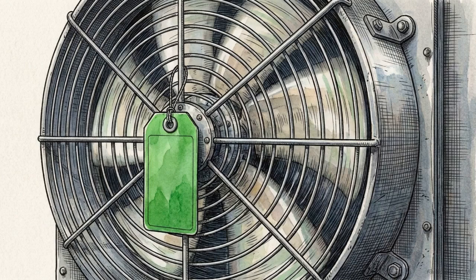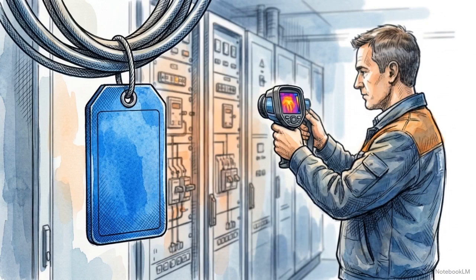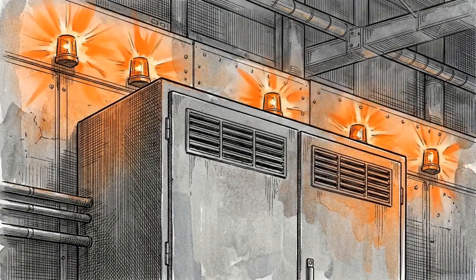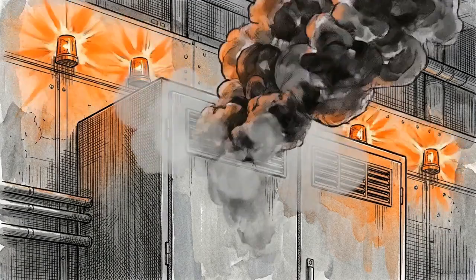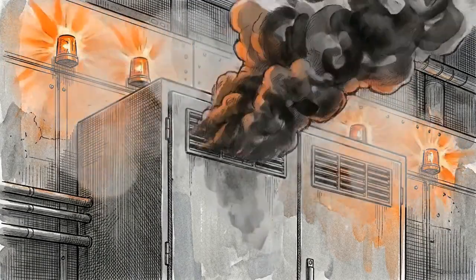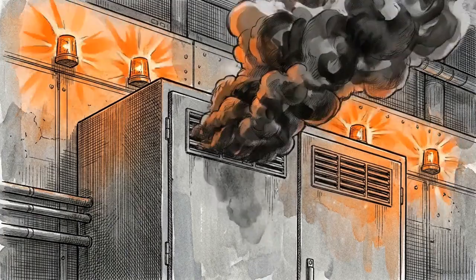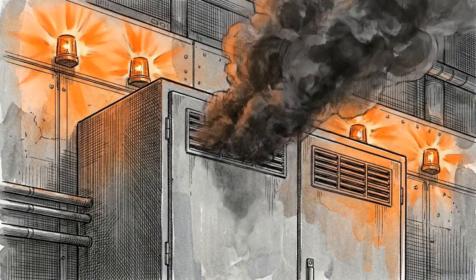Individual equipment startup and pre-functional readiness are confirmed at the CxL3 Green Tag stage. The CxL4 Blue Tag validates the performance of the entire system, providing the data required to prove capacity and functional response. Bypassing these gates allows unseen defects to remain in the infrastructure. This renders subsequent reliability tests inaccurate and places the future operational foundation at risk.